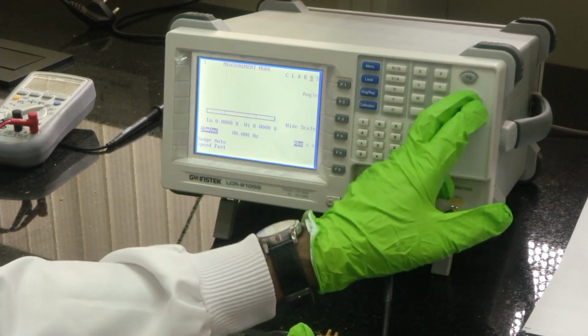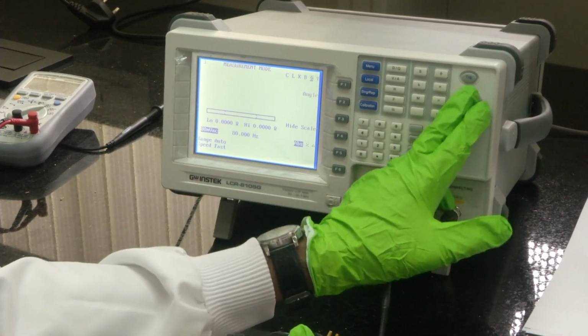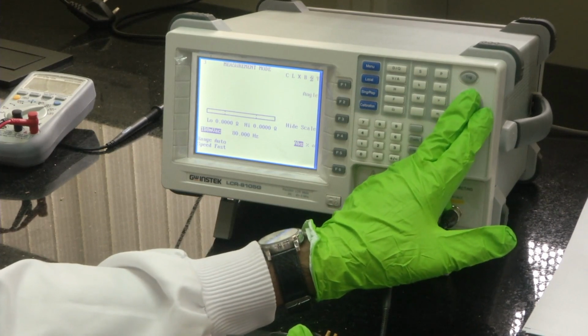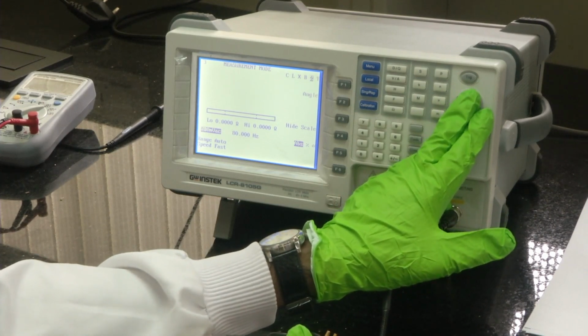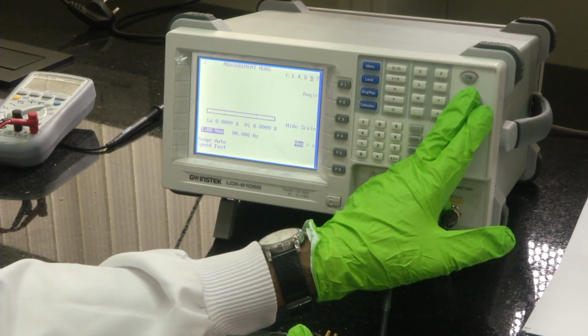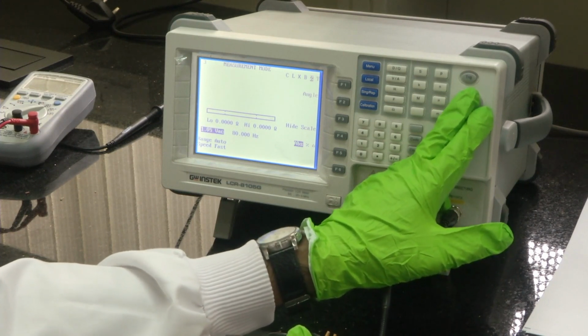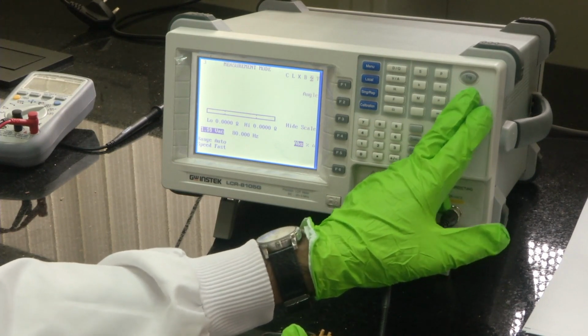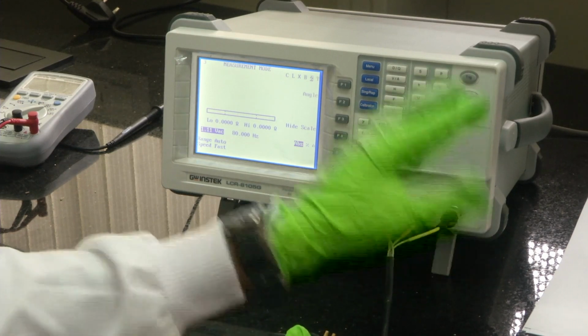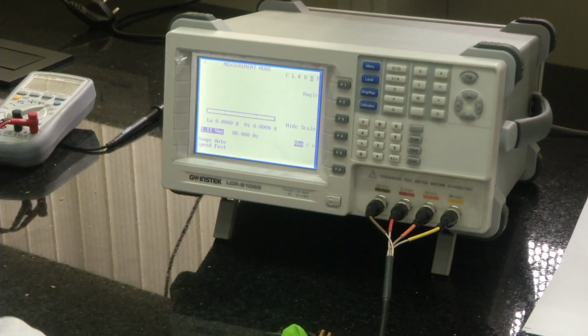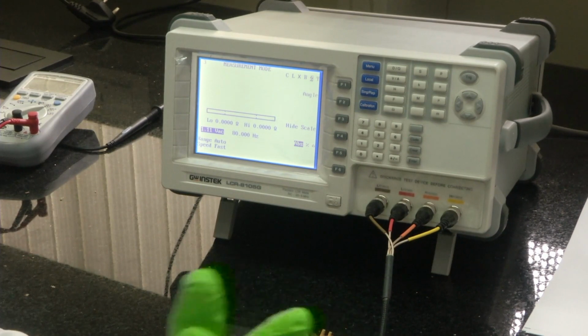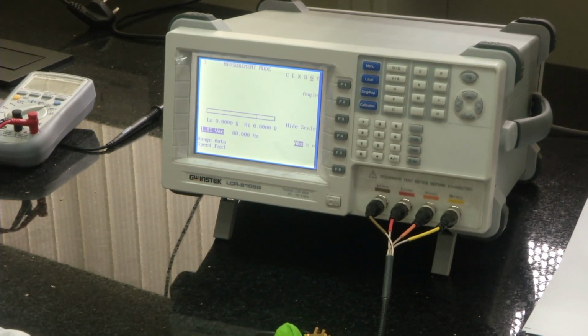I can even change the force voltage: 20 millivolt, 30 millivolt, up to 1 volt it can go. It can even go more than that actually. So, as you can see, but usually we use 10 millivolt as the drive voltage. Why so? Because we should not destroy or hamper our sensors while we test it. Our testing, as much as possible, should be non-destructive testing.